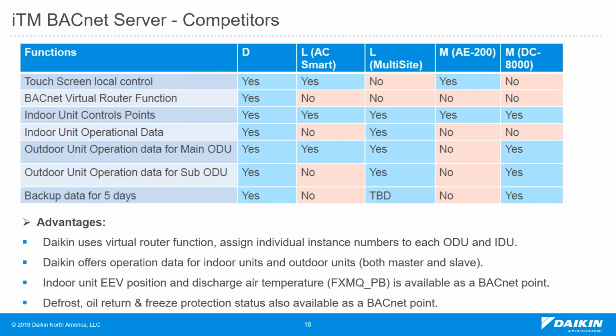If we compare our ITM versus LG and Mitsubishi BACnet server devices, our ITM has touch screen control, and so do the AC Smart from LG and the AE200 from Mitsubishi. The BACnet virtual routing function is only available from us, so that means every indoor unit and every outdoor unit system acts as one device. We also synchronize the name, so whatever name you put in the ITM will show up on the BACnet network. All the data points under each device are the same for indoor units, which provides a good way for the integrator to create graphics or programming in the front end. Much easier for them to use.